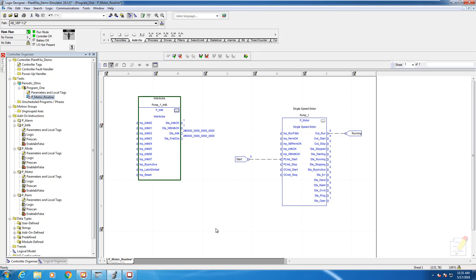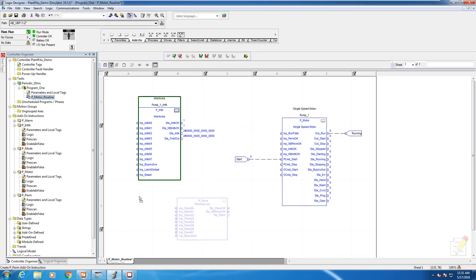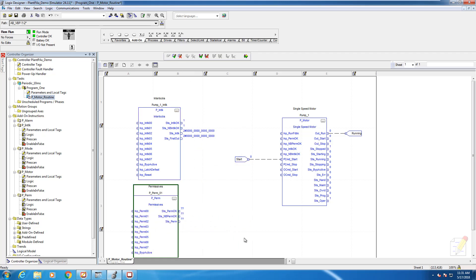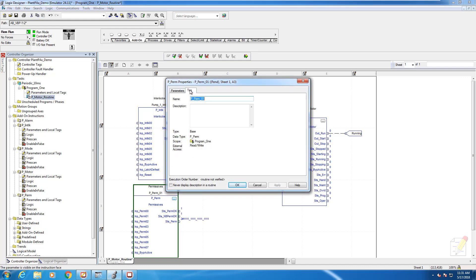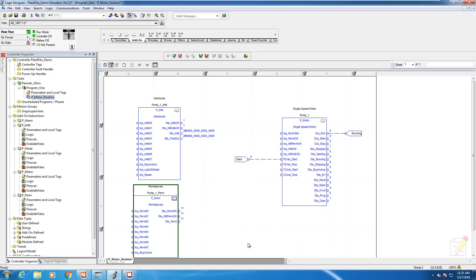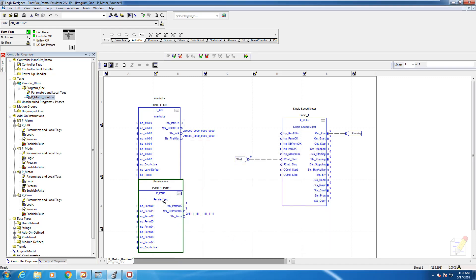We're going to do the same thing by bringing in the permissive block. There's a permissive block instance added to our program here. Once again, exact same naming convention: it's going to be pump one underscore PERM for permissive. By doing that, the motor faceplate will automatically recognize the fact that that permissive block is wired to it.